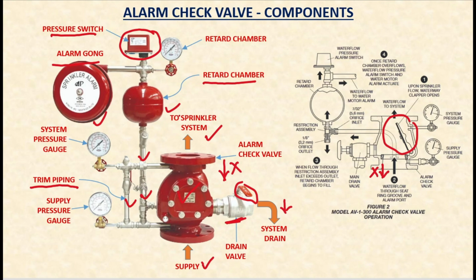The pressure switch can also be used to activate the fire pump when the pressure falls below a set limit. Suppose your pump is set to some limit, let's say 60 or 80 psi. So this pressure switch can send a signal to the pump to start the pump. So in summary, the primary function of a pressure switch in the fire system is to detect changes in water pressure, activate alarms, and sometimes control pumps.